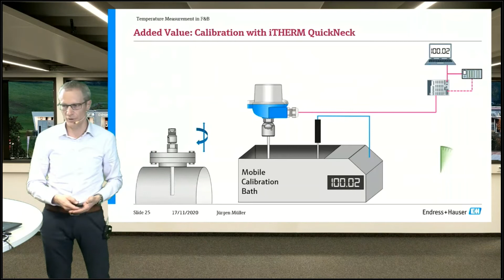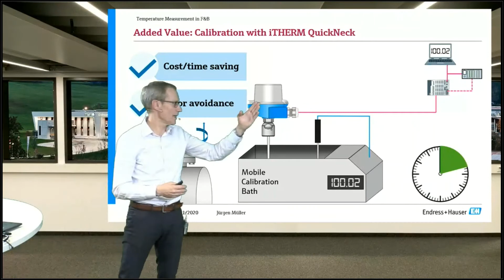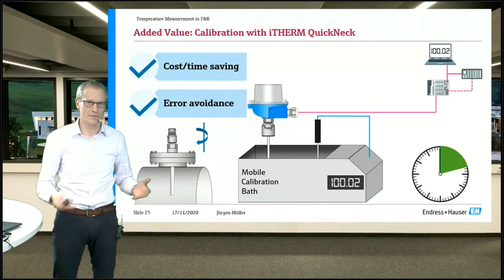Another very positive effect of the Quick Neck is that you never need to open the terminal head to access the transmitter or disconnect wires. So there's no chance of wrong connections when you put back or dismount the sensor, and no chance that water would enter the terminal head and cause corrosion or similar issues. It's just safer to use a thermometer with a Quick Neck than without that accessory.